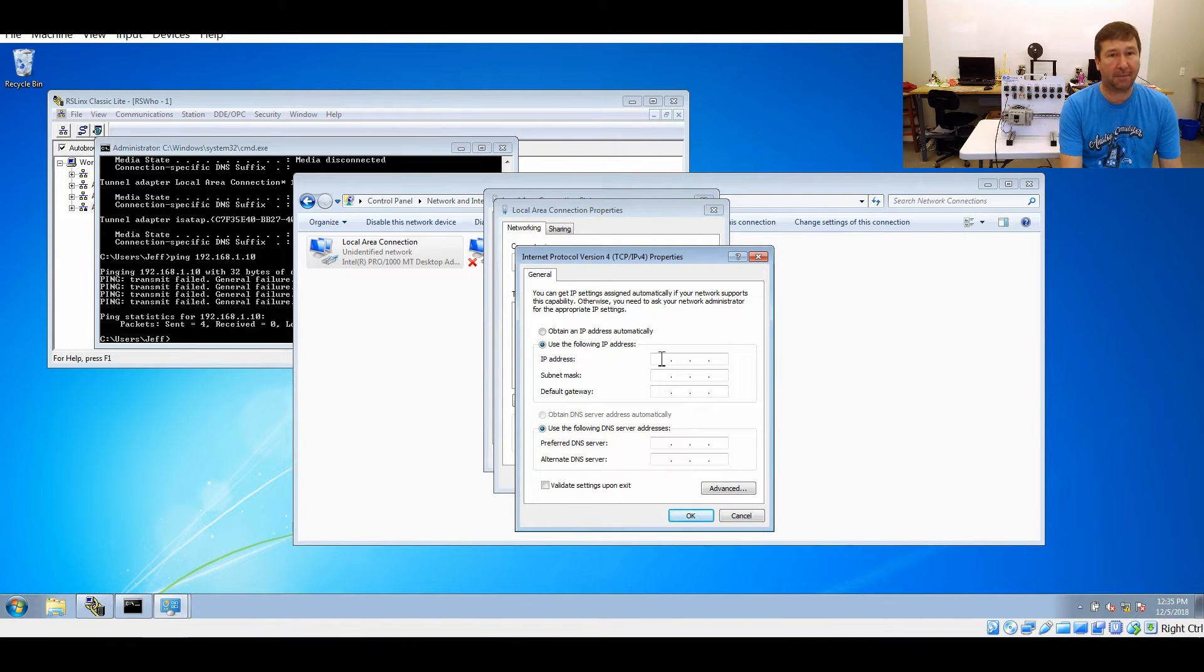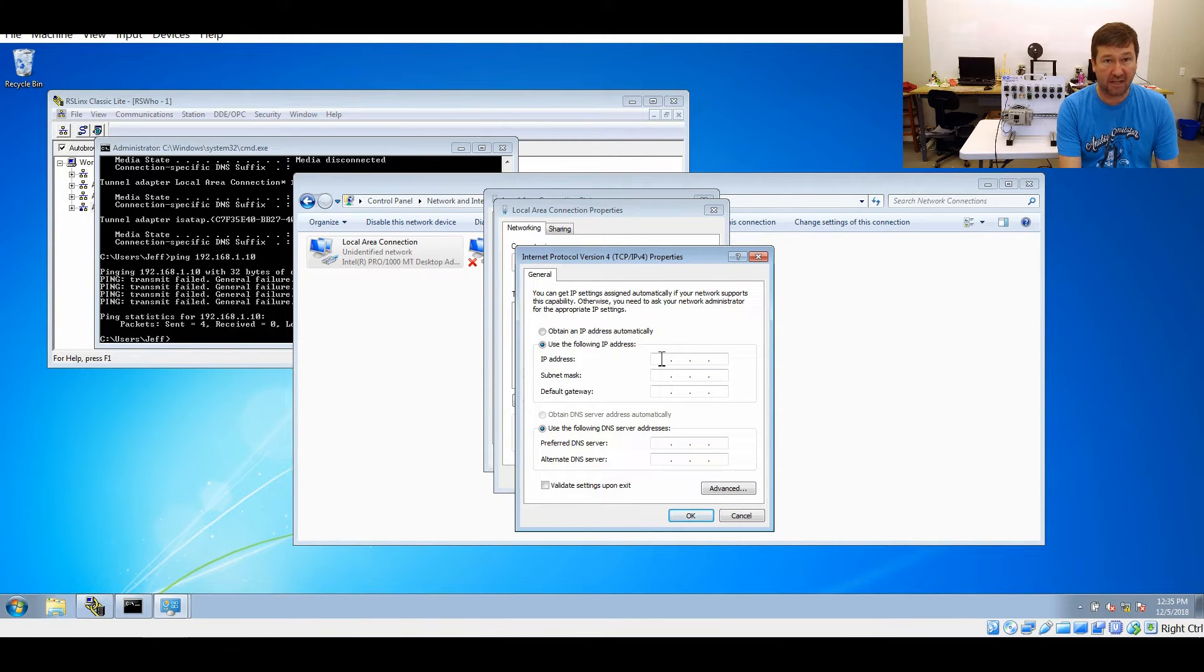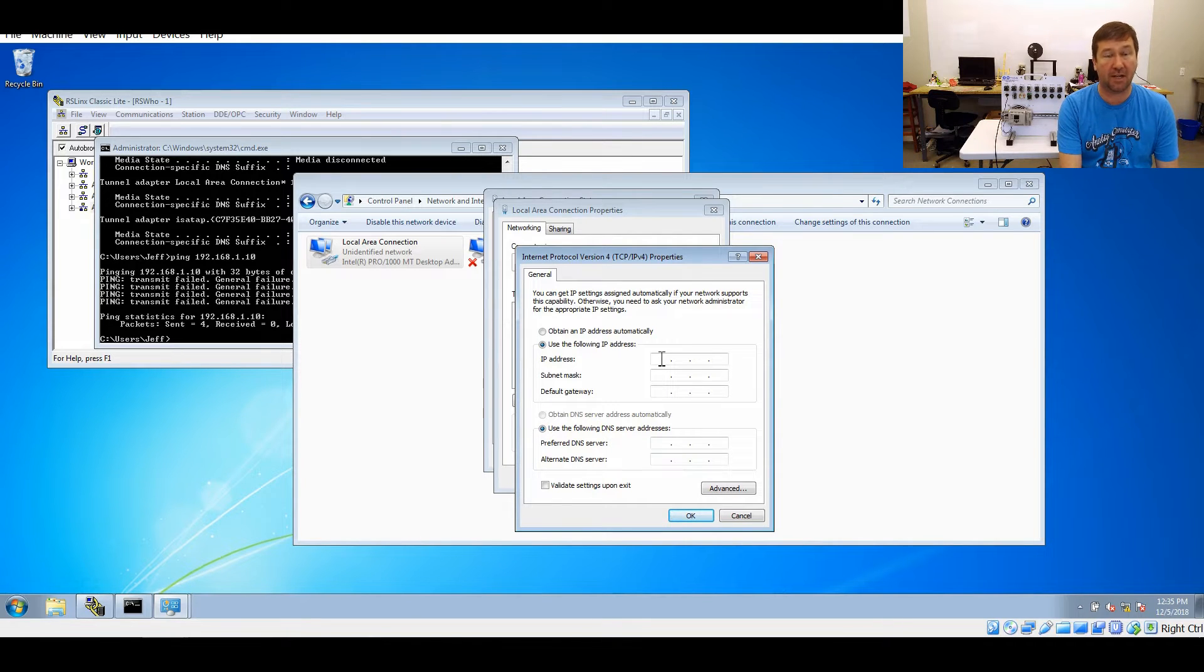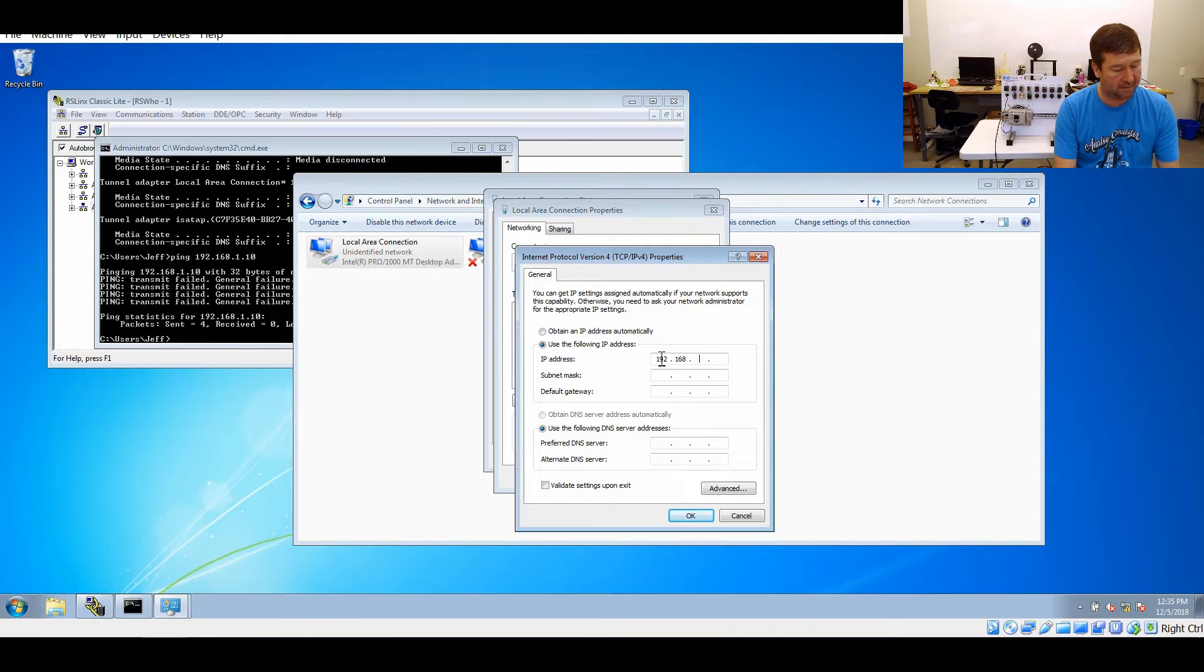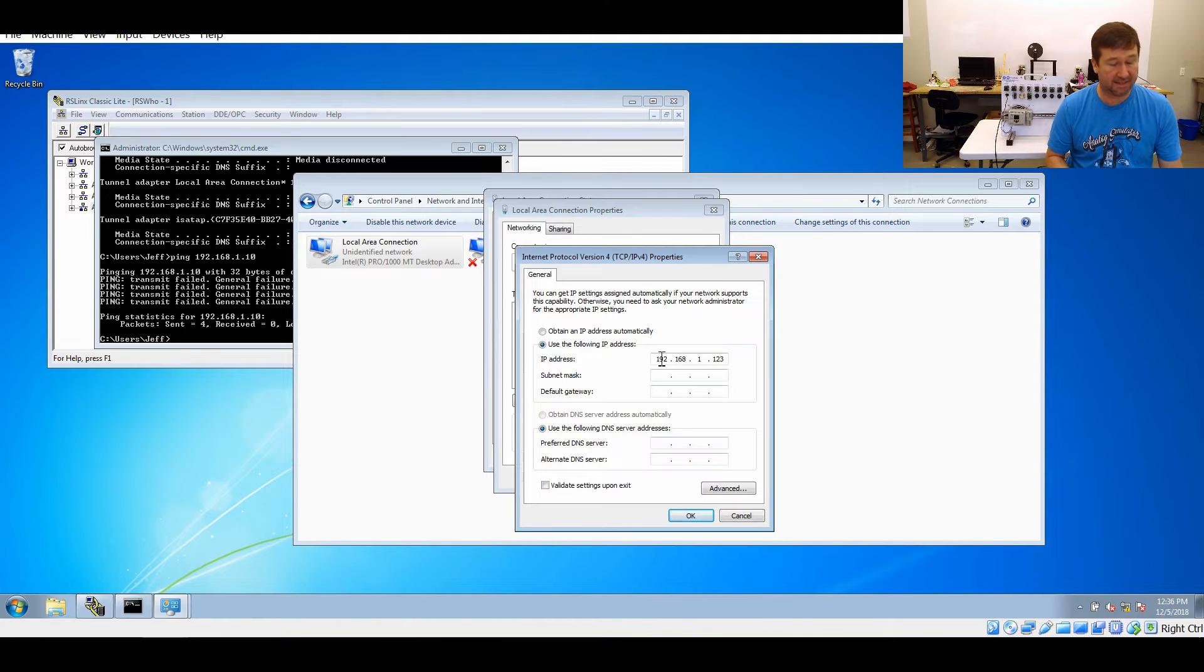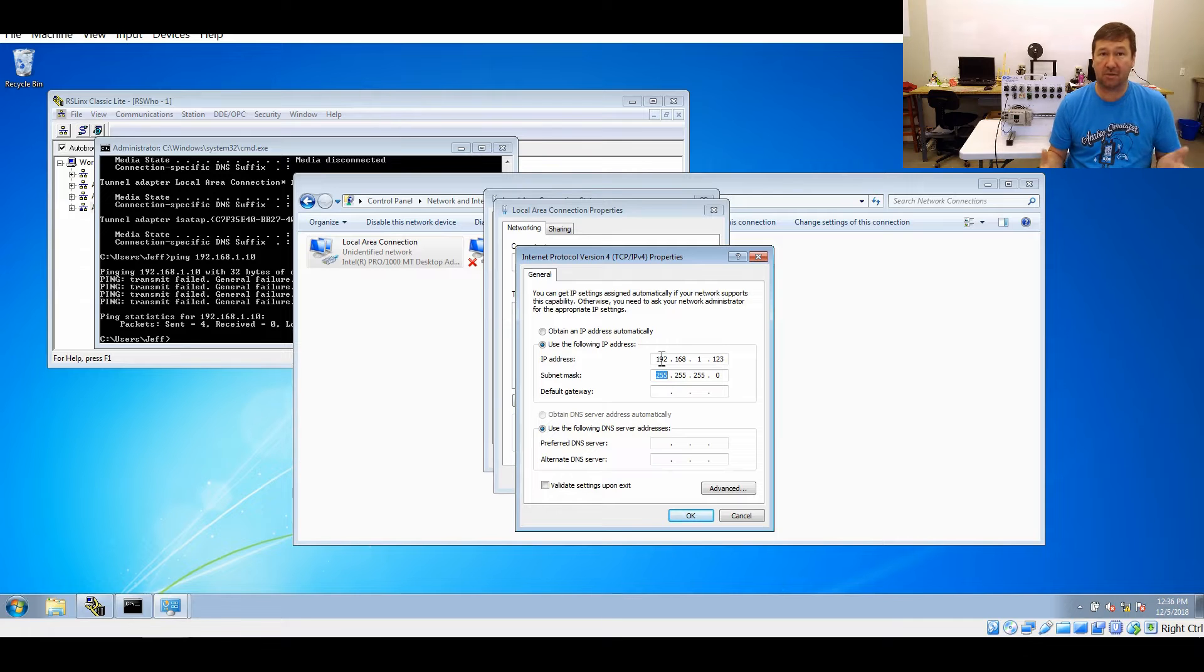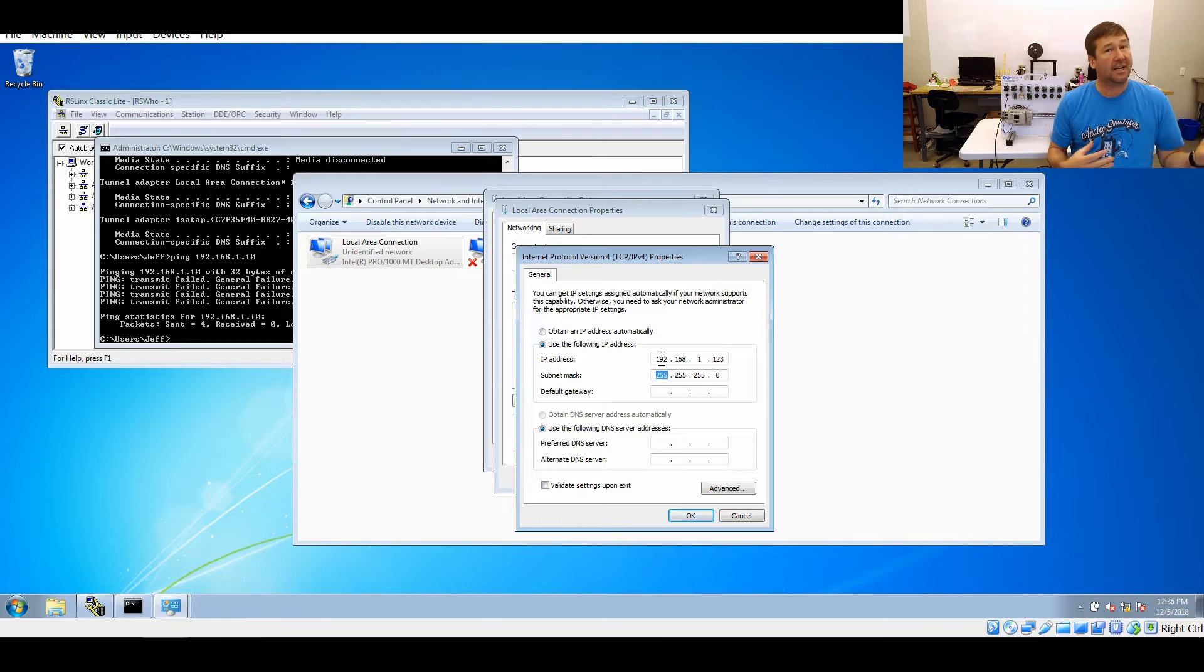Once you type it in, now remember, the one IP address with my three-octet rule that you cannot type is the PLC's IP address, which is 192.168.1.10. So we're going to type 192.168.1.123. Along with that is a subnet. If you simply hit the tab key after that, it'll automatically put in 255.255.255.0, and that will work for communicating with your PLC.